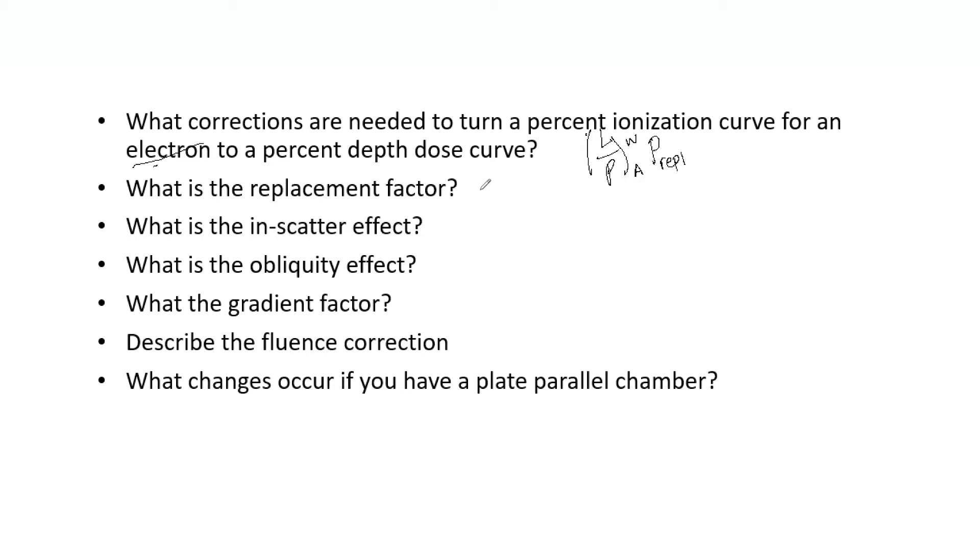So what is the replacement factor, this P replacement? This is essentially dependent on air cavity diameter and mean electron energy. It accounts for in-scatter. The replacement factor accounts for in-scatter, obliquity, and the gradient effect. We're going to talk about those here right now, but it's important to know what this P replacement actually does and the fact that these three things are all built into P replacement.